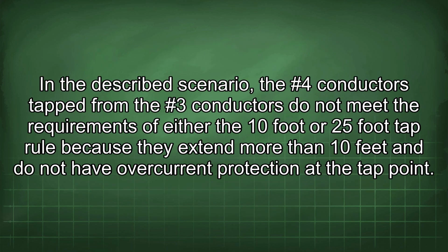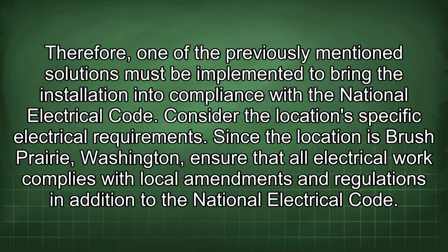In the described scenario, the #4 conductors tapped from the #3 conductors do not meet the requirements of either the 10-foot or 25-foot tap rule because they extend more than 10 feet and do not have overcurrent protection at the tap point. Therefore, one of the previously mentioned solutions must be implemented to bring the installation into compliance with the National Electrical Code.